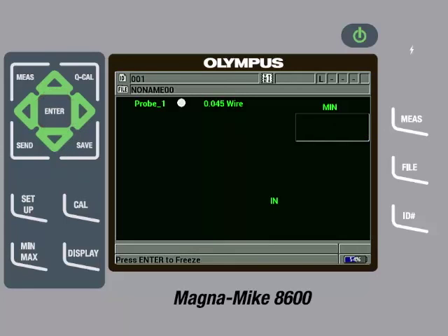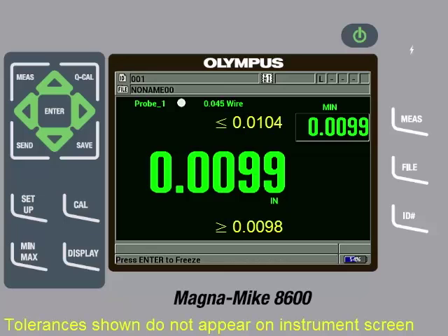Whenever you recall a calibration file, it is always recommended to remove the target from the probe tip and perform a QCal by pressing the QCal key. It is also good practice to then check a few reference standards to make sure the instrument is reading within specification and a new full multi-point calibration is not needed.